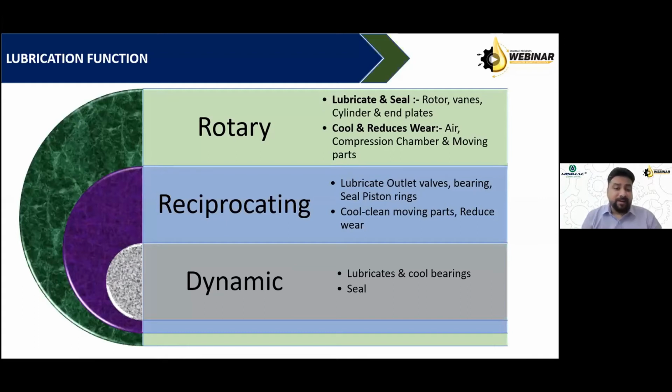The reason behind it is that the lubricant oil, which is filled in the compressors for lubricating the bearings, also serves as the working fluid. By working fluid, I mean the screw or the lobe or the scroll are all immersed in the lubricant, and the lubricant is serving as a working medium between the screws, between the lobes.